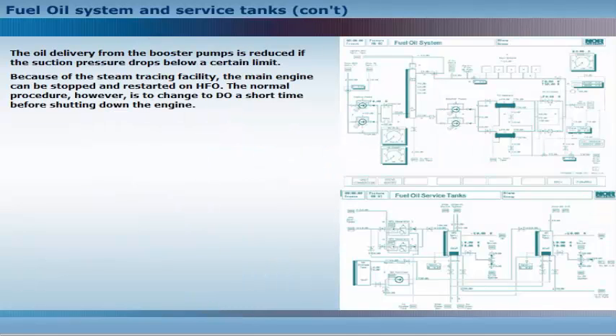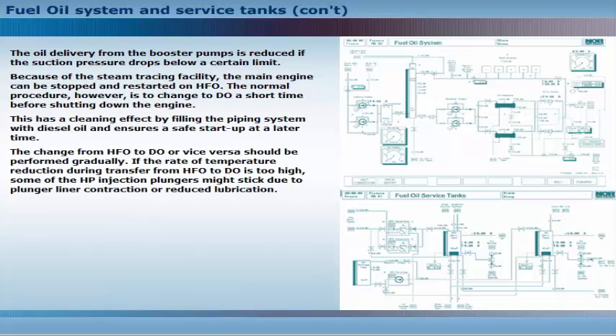The oil delivery from the booster pumps is reduced if the suction pressure drops below a certain limit. Because of the steam tracing facility, the main engine can be stopped and restarted on heavy fuel oil. The normal procedure, however, is to change to diesel oil a short time before shutting down the engine. This has a cleaning effect by filling the piping system with diesel oil and ensures a safe start-up at a later time.